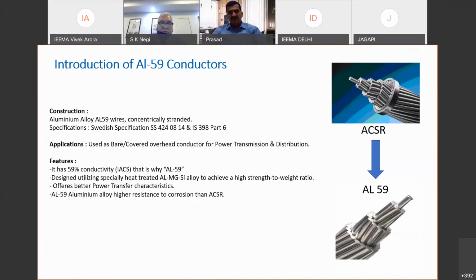As we have seen, being a conductor manufacturer, during the heating process we are getting rid of some inbuilt stresses. And at the metallurgical level, this conductor has the best corrosion resistance compared to other varieties of conductors available to the industry. So this would be the best choice for our coastal areas or some urban areas wherein the line is passing through some industrial zone or some pollutant-prone zones. So this conductor would be the best solution for the power transmission and distribution sector.